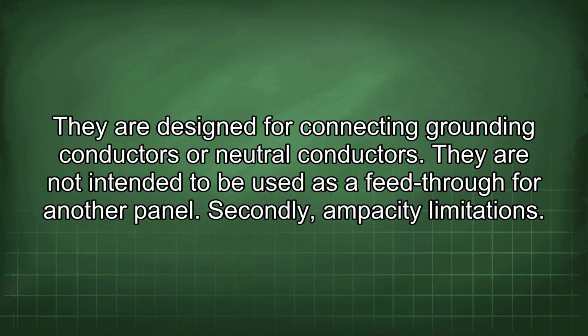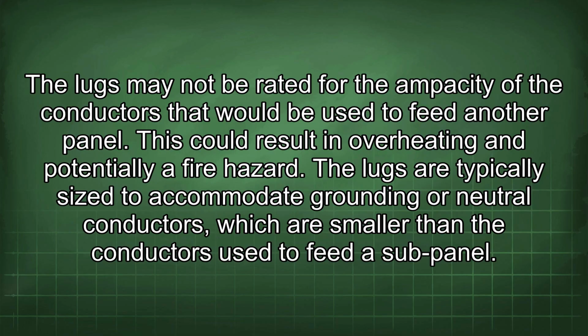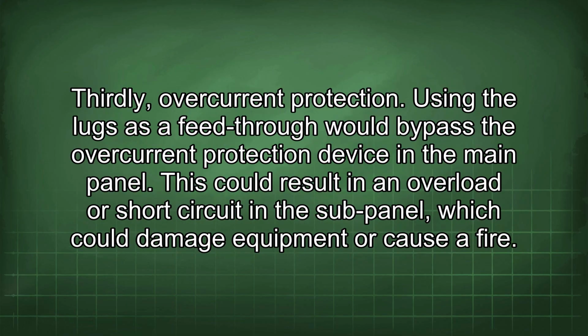Secondly, ampacity limitations. The lugs may not be rated for the ampacity of the conductors that would be used to feed another panel. This could result in overheating and potentially a fire hazard. The lugs are typically sized to accommodate grounding or neutral conductors, which are smaller than the conductors used to feed a sub-panel. Thirdly, overcurrent protection. Using the lugs as a feed-through would bypass the overcurrent protection device in the main panel. This could result in an overload or short circuit in the sub-panel, which could damage equipment or cause a fire.